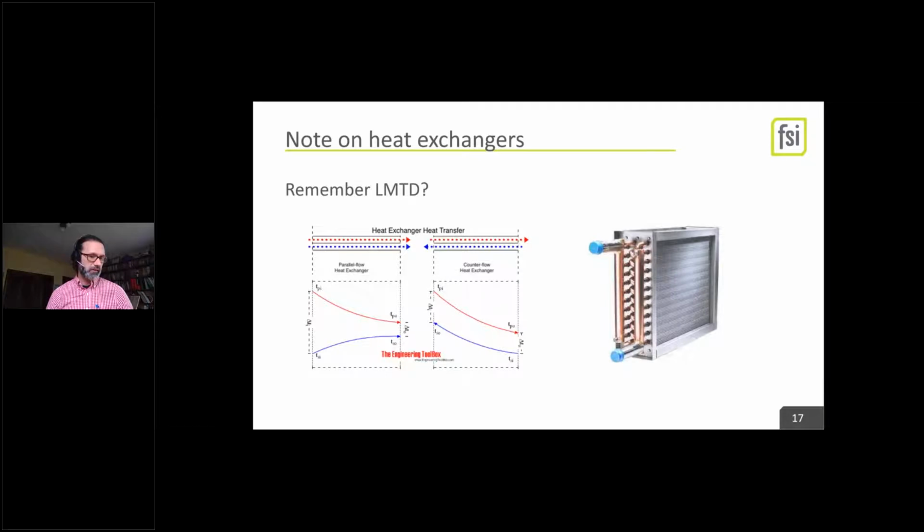So this will be particularly useful for mechanical engineers and maybe a modest education for everyone else. Heat exchangers can only get so much heat transfer theoretically. A hydronic coil in an air handler is a heat exchanger. It's exchanging the heat in the water with the heat in the air, or when you're cooling, it works the other way. The heat in the air is going into the water, and you go back to your chiller and cool down again.